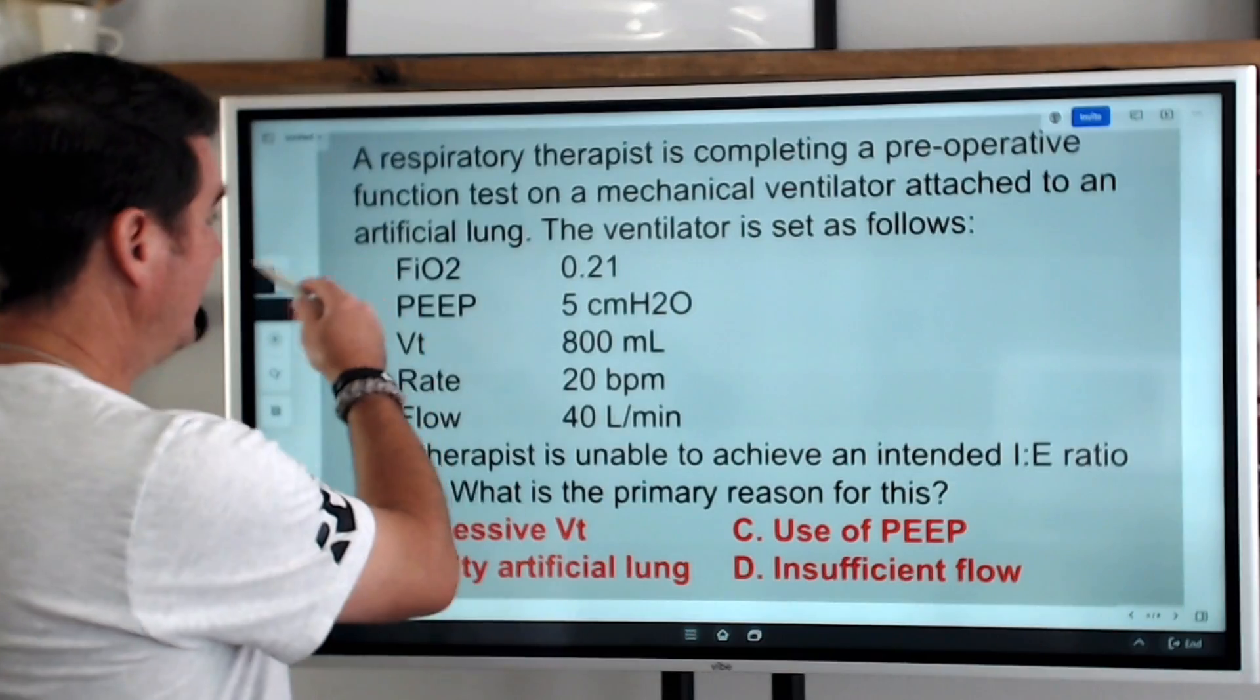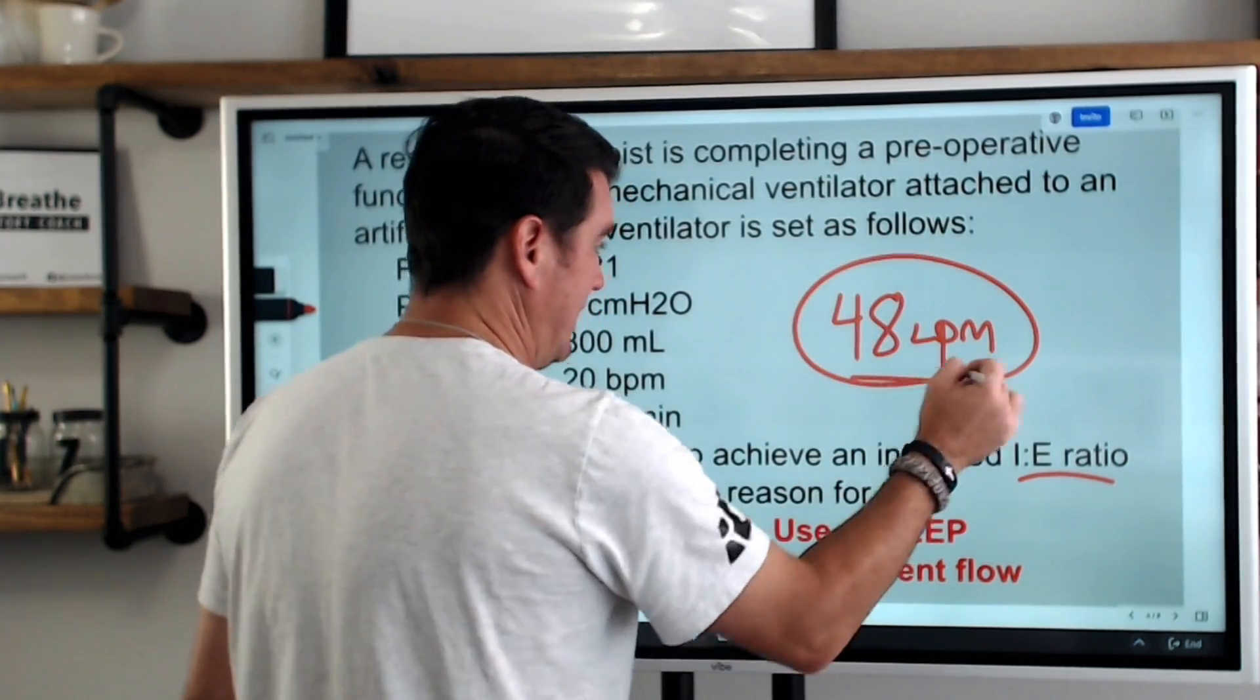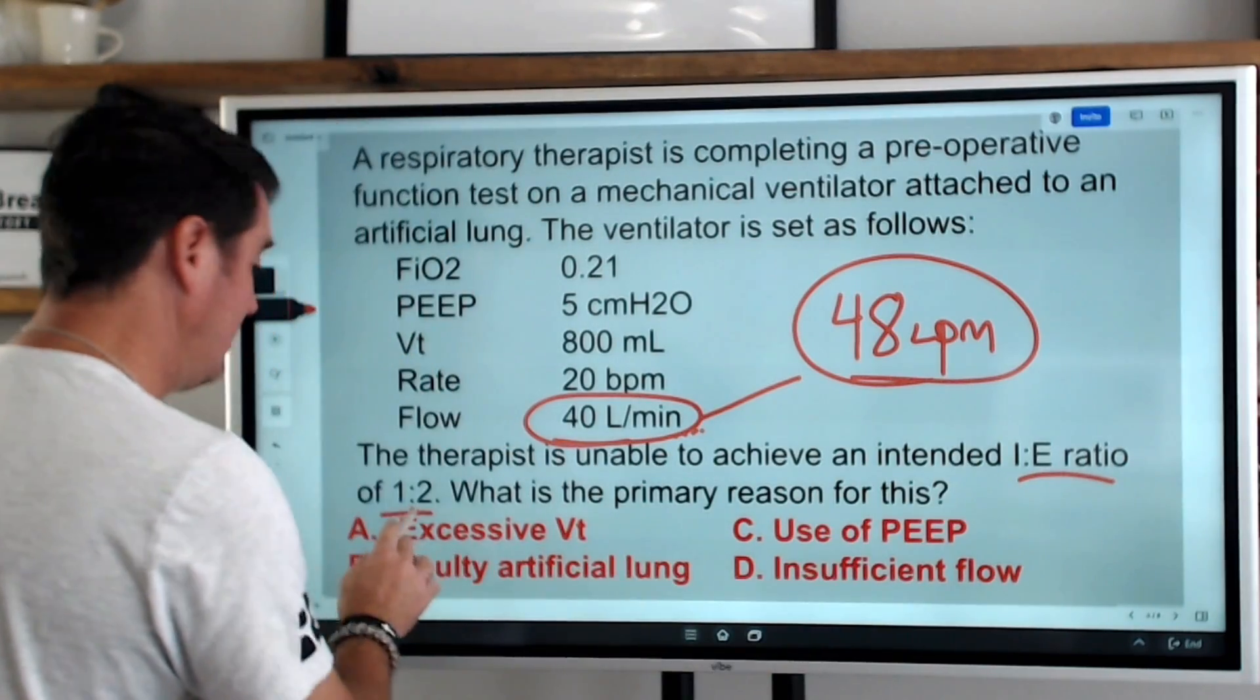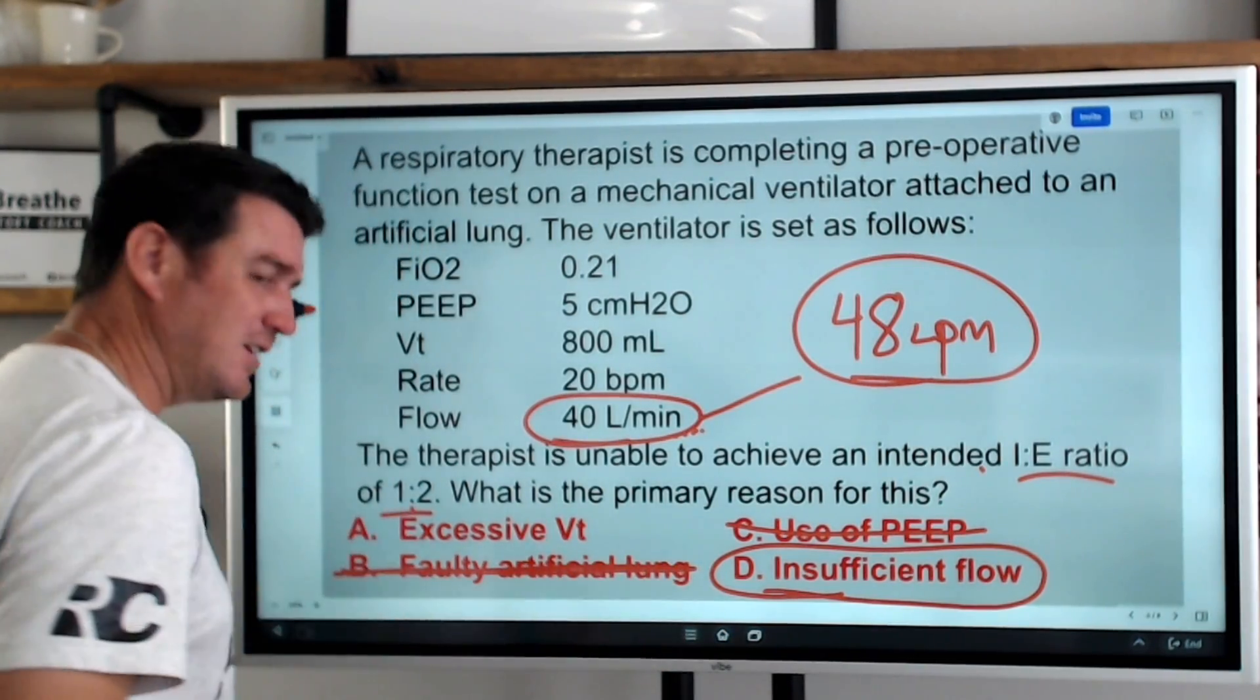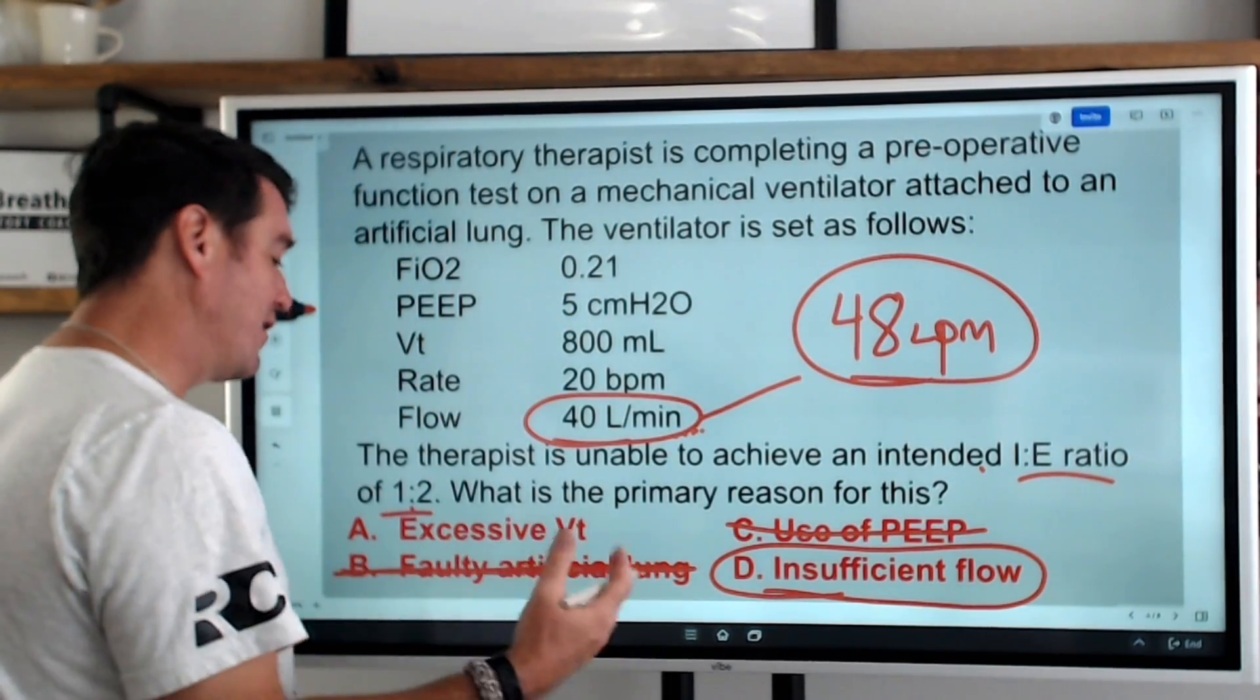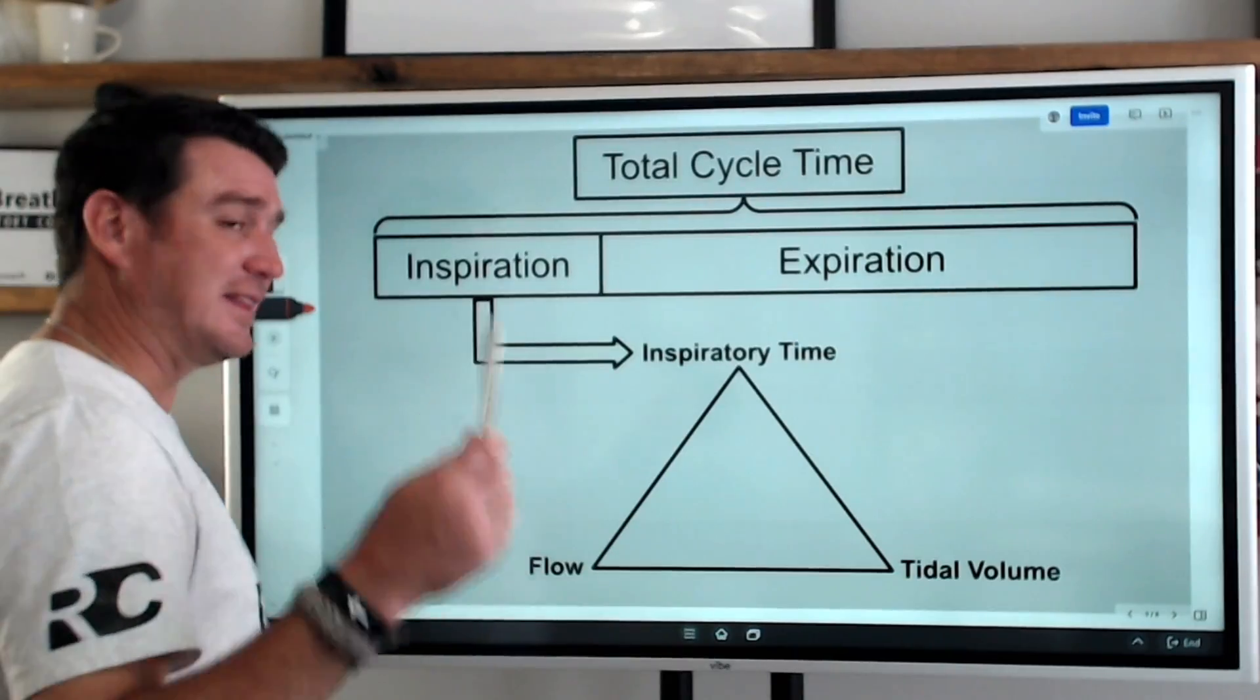Let's go back to the question here. All the settings back here. What is the primary reason that we cannot achieve this I to E ratio of one to two? Remember, we know that we need 48 liters per minute, but we are set on 40 liters per minute. There's a problem. This is why the one to two is not being achieved. The answer here is insufficient flow. I already told you the use of PEEP. PEEP has nothing to do with I to E ratio. The faulty artificial lung, nothing to do with I to E ratio. It may have something to do with a leak. If you can't get a return volume back, maybe you have a faulty artificial lung, but other than that, no. And it's not an excessive tidal volume because we are testing this tidal volume. Okay? So it's not a tidal volume. The problem here is we don't have an adequate flow, which I told you 90% of the time I to E ratio questions think flow. This is what we're talking about.